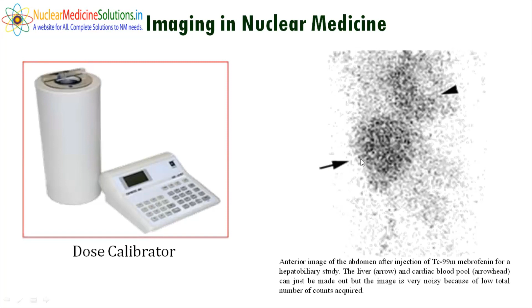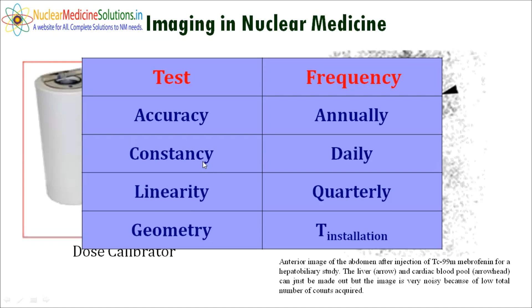So to check the performance of the dose calibrator, whether it is working properly or not, we can perform certain tests. These are listed in this table: accuracy, constancy, linearity, and geometry. So what is the significance of quality control in a SPECT system?